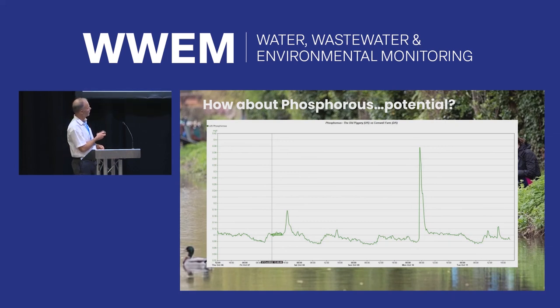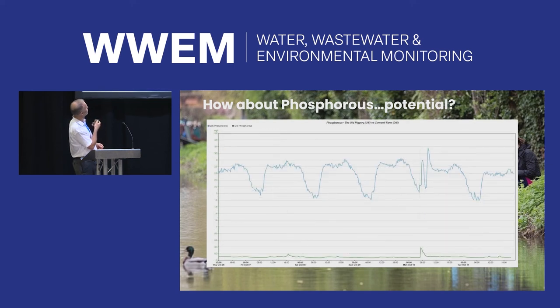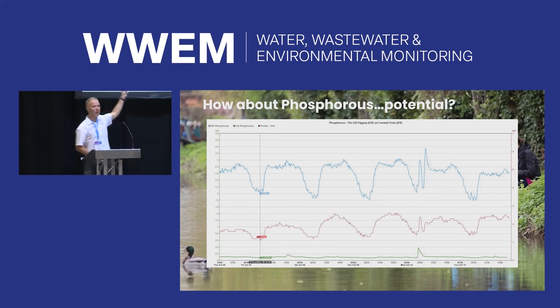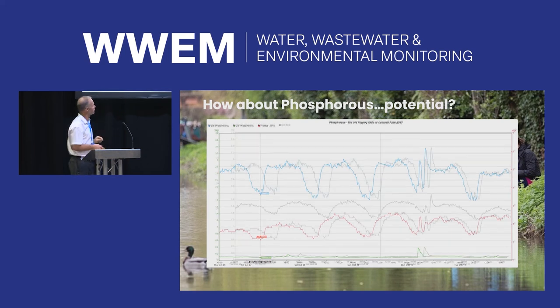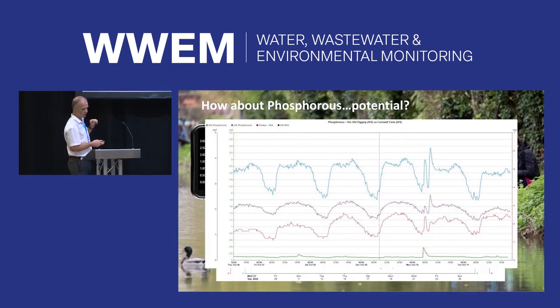And here's the calibration applied now to an upstream and downstream. So this is just phosphorus. So you've got 0.1 typically. And then when we add the downstream, we're getting about 2.5. And you can see the peaks here. What's really interesting, you can see this peak here. If you look carefully, you can see it in the downstream, superimposed on top of the treatment works. There's a bigger one there as well.